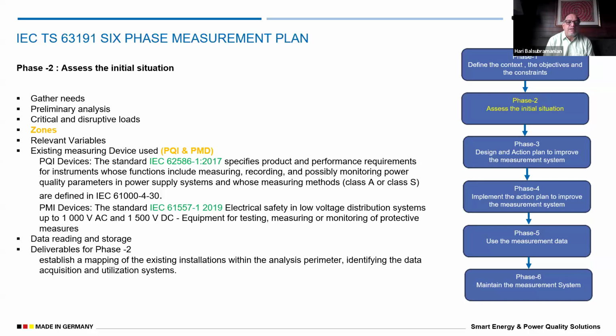As per the standards, these devices are defined under 62586 for PQI, and PQI is further defined in a much better, latest standard called 61000-4-30, as Class A and Class S devices. Then the standard 61557 covers the PMI devices.